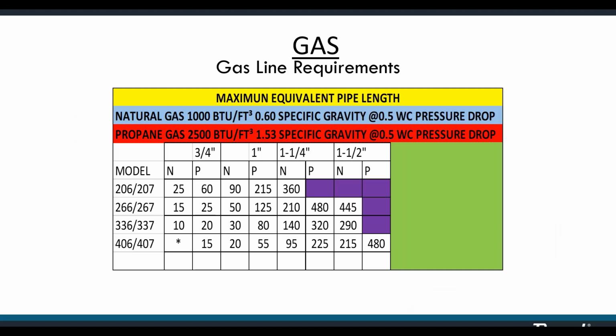Let's move on to gas. These are the gas line requirements. The larger the heater size and the further the distance from the regulator, the larger the pipe diameter must be. You can't expect to deliver enough gas to a 400,000 BTU heater using 50 feet of 1-inch pipe. The pipe's just not big enough to move enough volume. This is just physics. Okay, again, not a Raypak thing. This is a physics thing. You will find that these distances and sizes are similar across all heater manufacturers as they are related to NFGC guidelines.